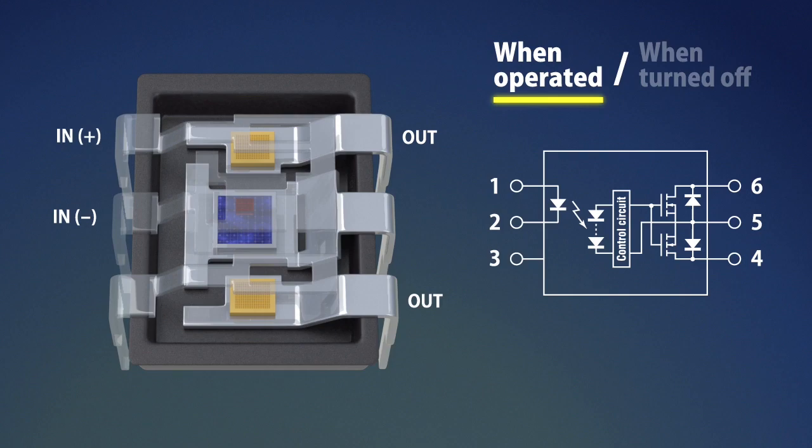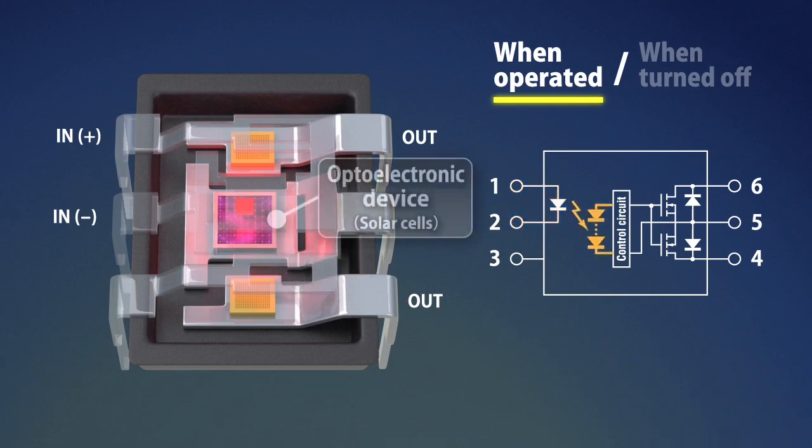How PhotoMOS operates: During operations, when current flows to the input terminal, the LED on the input side emits light. The emitted light passes through transparent silicone and reaches the photoelectric element which is mounted opposite to the LED.